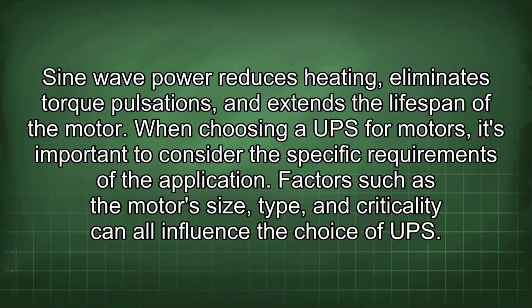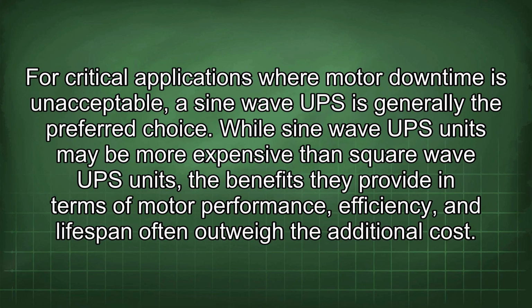When choosing a UPS for motors, it's important to consider the specific requirements of the application. Factors such as the motor's size, type, and criticality can all influence the choice of UPS. For critical applications where motor downtime is unacceptable, a sine wave UPS is generally the preferred choice. While sine wave UPS units may be more expensive than square wave UPS units, the benefits they provide in terms of motor performance, efficiency, and lifespan often outweigh the additional cost.